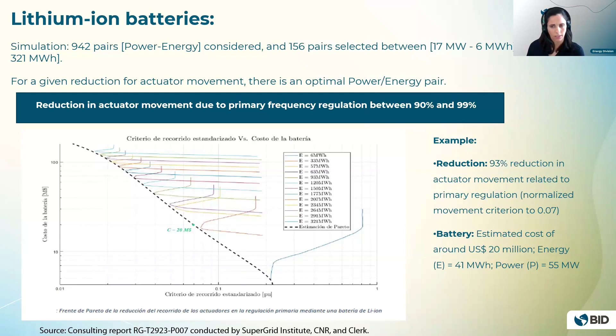Next one, please. For the batteries, 942 power-energy sizing pairs were considered and 156 pairs were selected in the area of interest between 17 megawatts and 6 megawatt hours and 346 megawatts and 321 megawatt hours. The simulation provided access to the set of economically optimal power-energy pairs to reduce actuator movements, as shown in the graph below. It can be observed that the selected technologies reduce actuator movements due to primary frequency regulation by between 90 and 99%. And for a given reduction in movement, there is indeed an economically optimal solution.